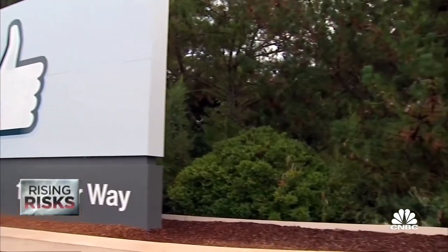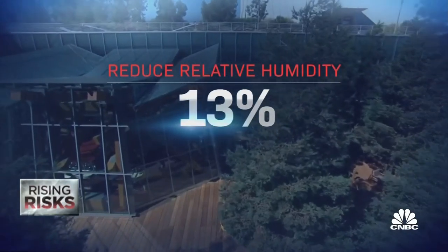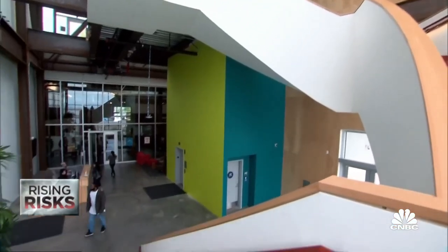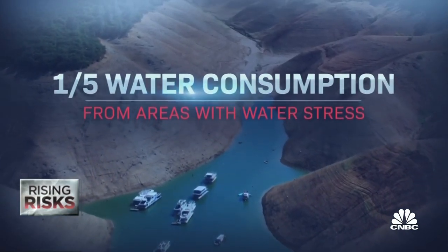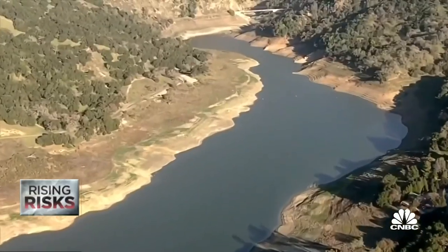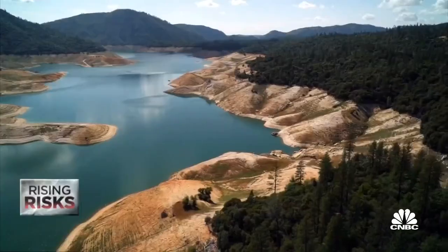Realizing the risk in New Mexico, Meta ran a pilot program on its Los Lunas data center to reduce relative humidity from 20 percent to 13 percent, lowering water consumption. It has since implemented this in all of its centers. But Meta's overall water consumption is still rising steadily, with about one-fifth of that water last year coming from areas deemed to have water stress. It does actively restore water and set a goal last year to restore more water than it consumes by 2030, starting in the West.